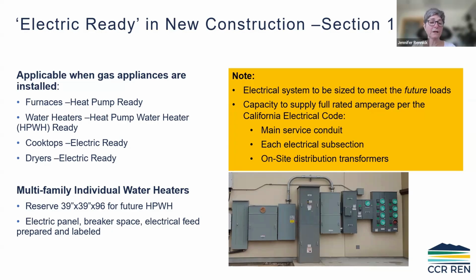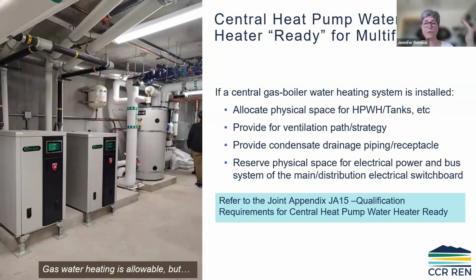It's the only place in the code that spells out a reserve size for a heat pump water heater. But I'm finding that if you have that kind of an area for any of your closets for heat pump water heaters, then it's usually big enough to put in everything you need. And then there's some clarification that for the electric ready, your electric system has to be designed to meet these potential future loads. So for the central heat pump water heater, this is a new section.